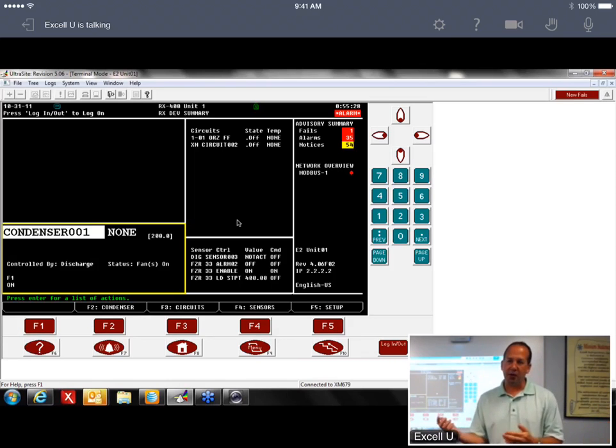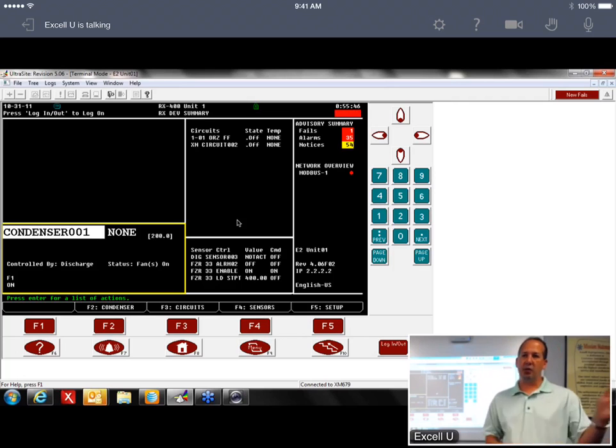The reason we had the circuit is if you had 3 cases on a circuit, you'd have one XM circuit but 3 XM devices. You don't want to go into each of those devices to set your set point or defrost, because it's the same for all 3, so it doesn't make sense to set it up in 3 different places. So we have the XM circuit that overrides and pushes it down to all 3 devices. Now the way Publix does it, they have one case as one circuit.